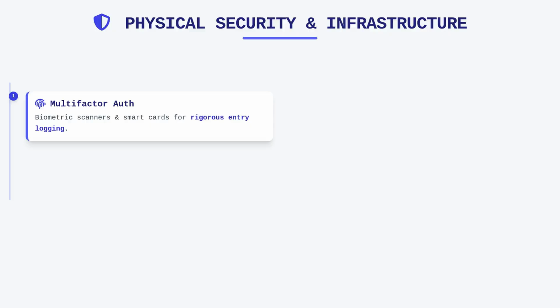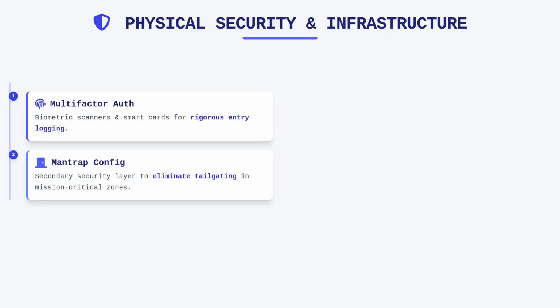Physical security acts as the final perimeter of our design strategy and should never be treated as an afterthought. Restricting access to the equipment room is critical, necessitating the use of multi-factor authentication, such as biometric scanners or smart card readers, to log every entry. For mission-critical environments, a mantrap configuration provides a secondary layer of physical security, preventing unauthorized tailgating into the secure space.